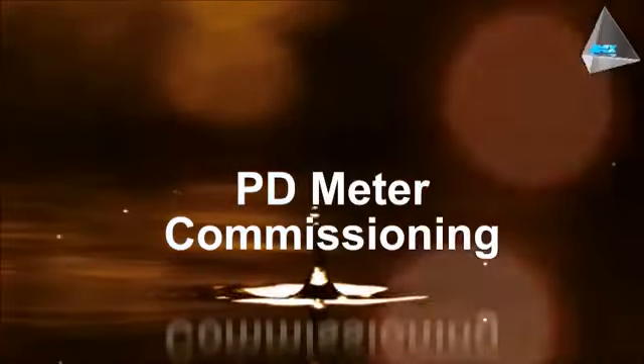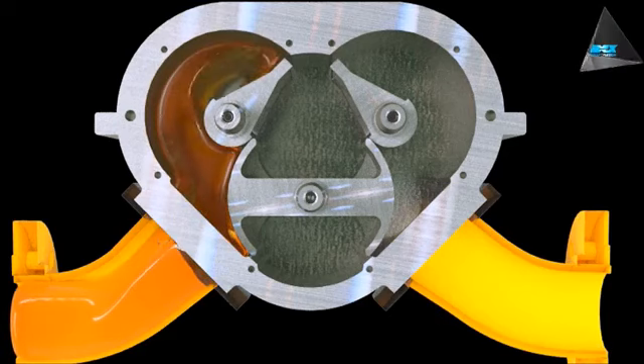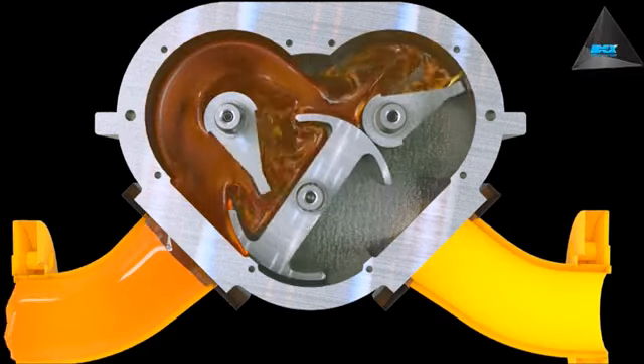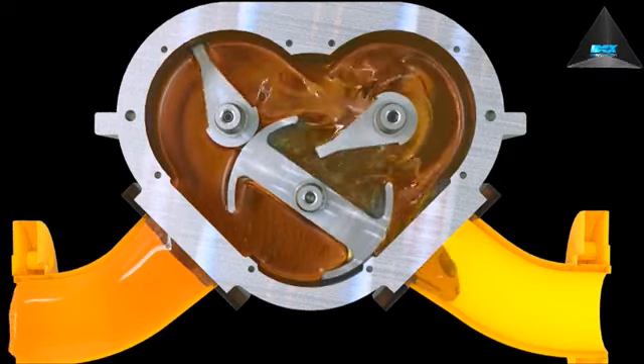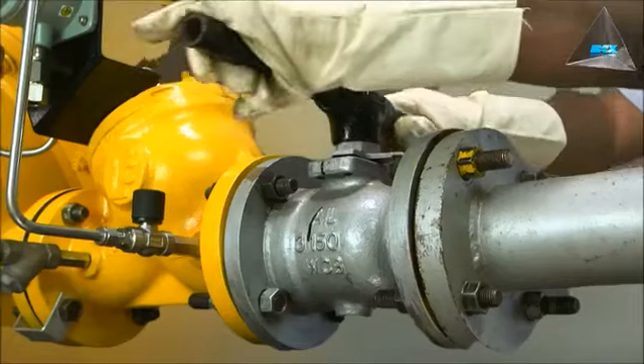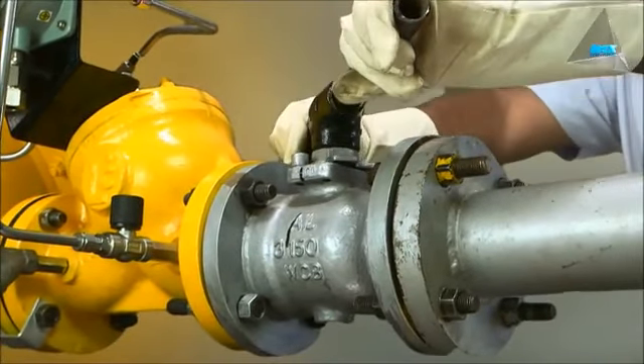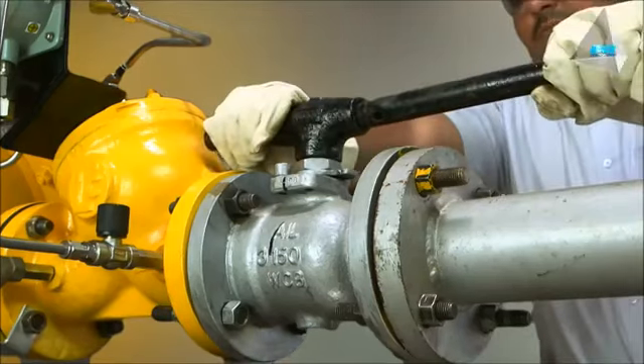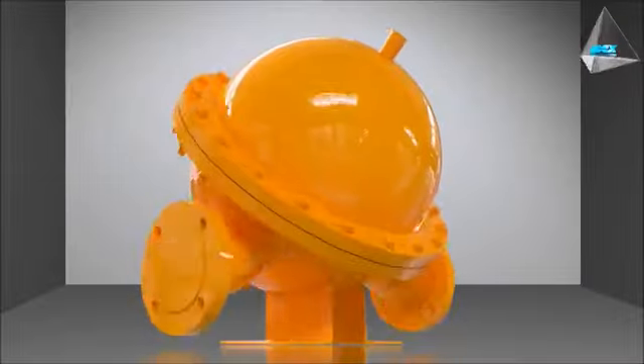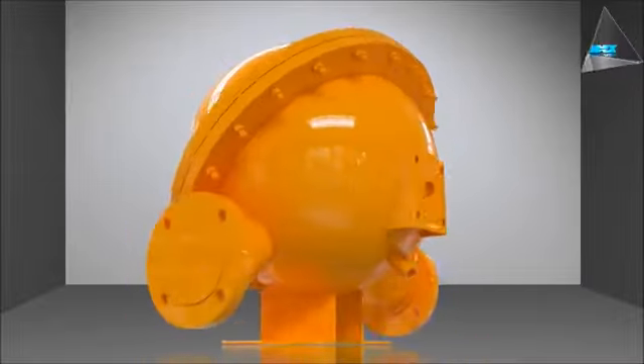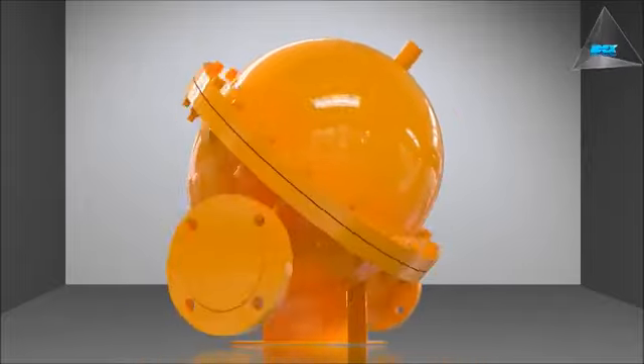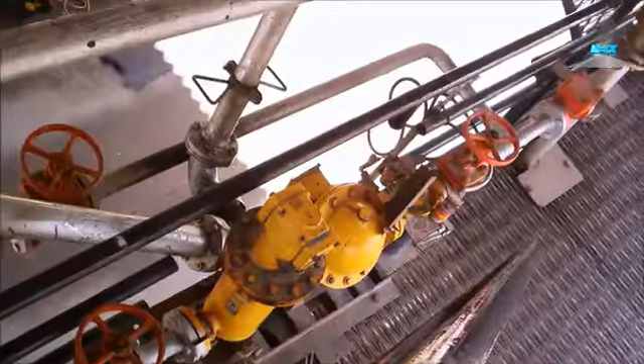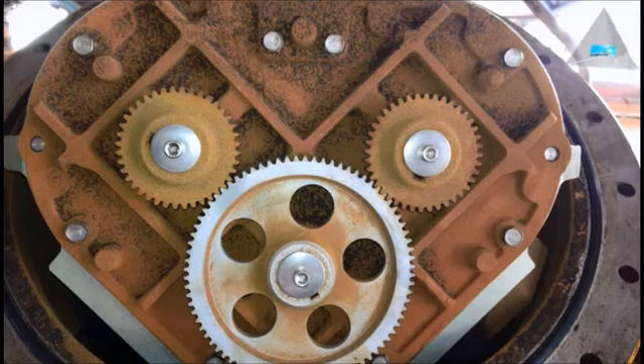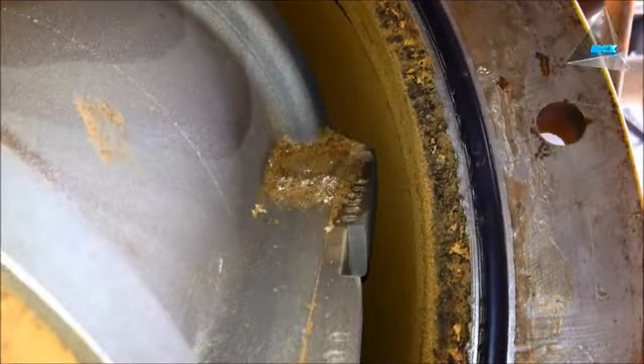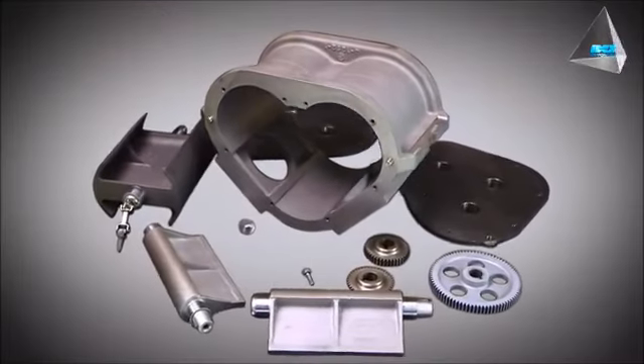PD meter commissioning. When taking the meter into operation, the system should be filled slowly with liquid to ensure that the meter does not rotate air or vapor at speeds higher than what it is rated for. Slow filling can be ensured by throttling the meter isolation valve. PD meter maintenance. A liquid-controlled PD meter requires little or no maintenance if properly installed and calibrated as per recommended practices for refined fuels. In the event of any corrosion in the piping and subsequent accumulation of foreign particulate matter, it is recommended at such instances only to open and clean the measuring chamber.